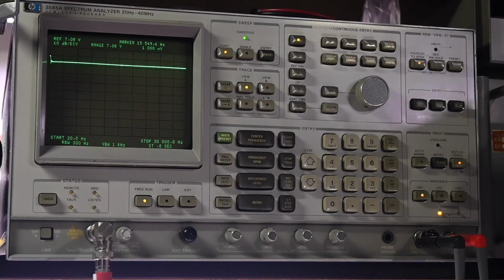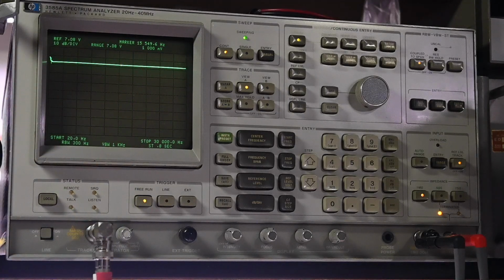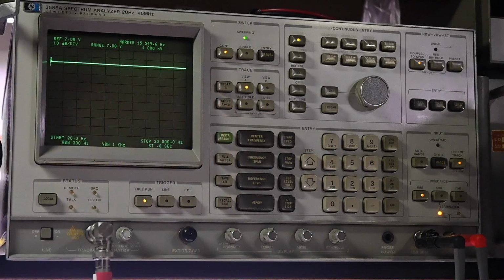That's very, very reasonable. And if I change the scale, those numbers and measurements might zero in and change just a little bit as well. But I'm not going to get into all of those types of detailed measurements in this case, because there's really no problems. It's looking perfectly fine. But one other thing I wanted to mention, if you are doing this type of measurement, this is not a logarithmic sweep. Okay, this is a linear sweep going across.